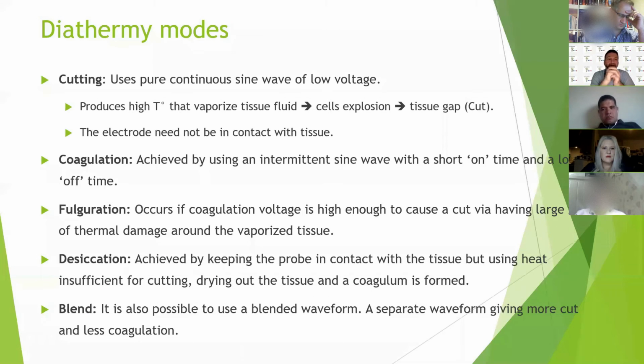To coagulation, however, you have an intermittent sine wave, but it has more power, and it goes on and then rests for a bit and then on again. Somewhere in between is fulguration, which is high voltage coagulation that causes something like an explosion of the tissues, which is a mixture of vaporization and coagulation. Desiccation is when you keep it in touch, but it's lower heat than cutting, so it dries only the tissue, and then it just coagulates. A blend is any mixture of the above.